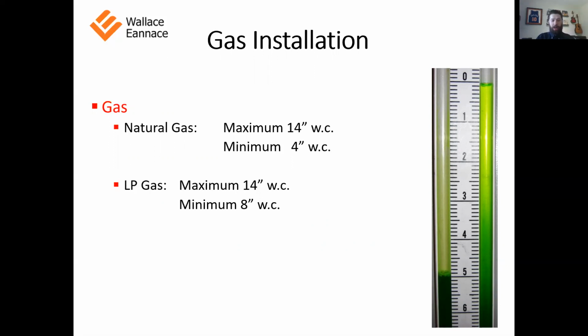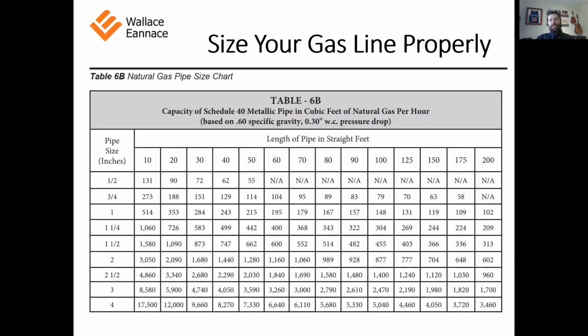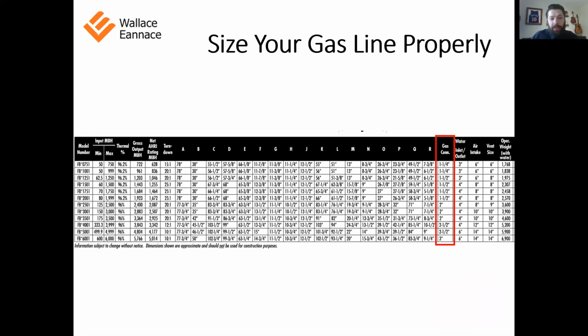And if that's the case, you're probably going to want to put on a lockup regulator just to make sure you have enough reservoir gas there. A common mistake, guys, is that the gas line does not get sized properly. If you look at this submittal for the Crest, you'll see the connection on a 1 million BTU unit, for instance, is 1.25 inches.